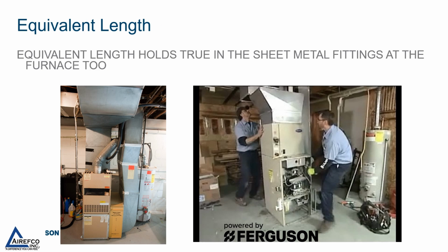Equivalent length also holds true in the sheet metal fittings at the furnace. You can easily add over 100 feet equivalent length by your choices of fittings coming off the air handler or the furnace. So choose your fittings and transitions wisely to reduce the equivalent length and turbulence in the system.